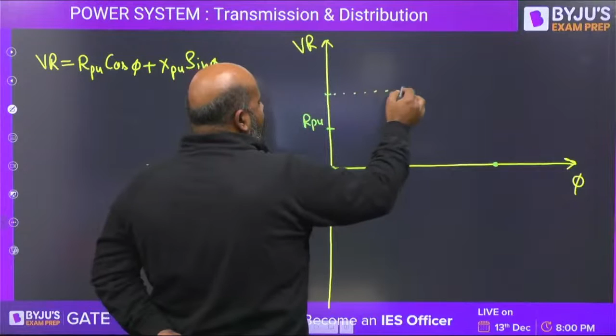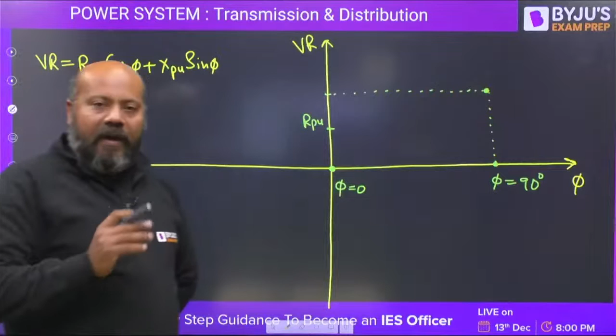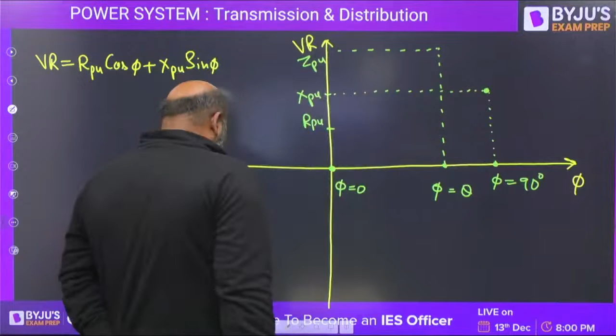It is going to be higher than R per unit because for a transmission line the X by R ratio is high. So you are getting this point. This is phi 0, this is phi 90 degree. Somewhere between 0 and 90 you get an angle where voltage regulation is maximum. That is when phi is equal to theta. When phi is equal to theta, the maximum voltage regulation value is Z per unit. This is X per unit.